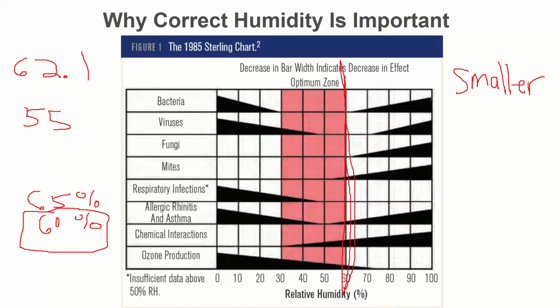It's very basic. I need lower airflow, less airflow. The lower the CFM, within a range of discussion here, changes the sensible heat ratio, and I can remove more moisture. I might get bigger evaporator coils, with more fins per inch or more rows of depth. I might put in sensors that babysit humidity, or thermostats with a humidity sensor that force the cooling on to dehumidify as well. There are a few other things we can do, but that's a whole other discussion.